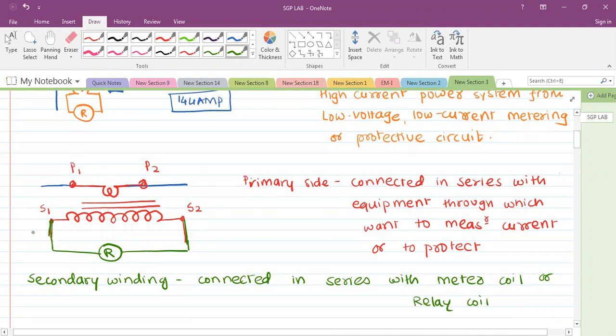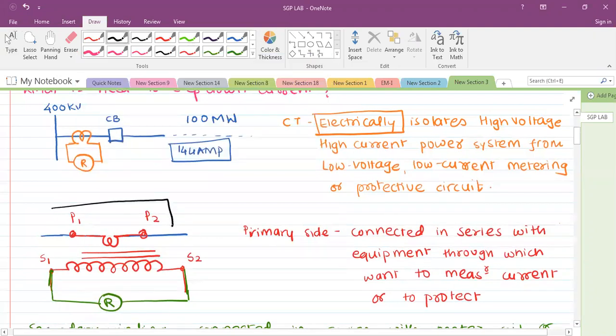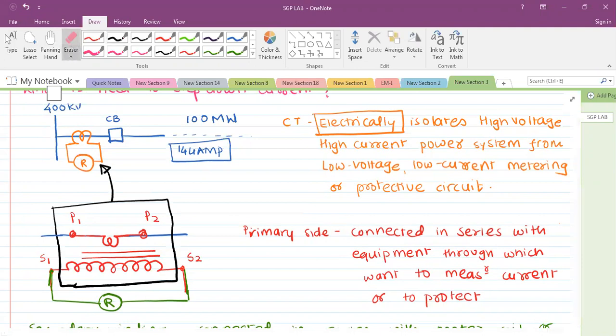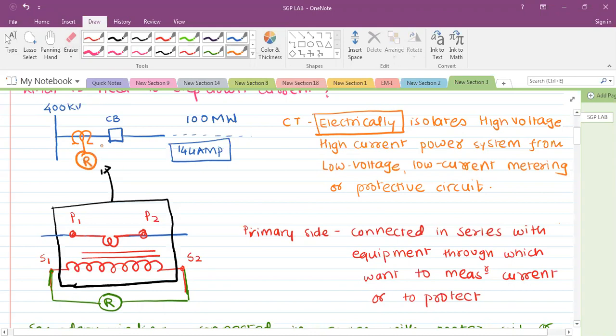Then understand, this is the symbolic representation that we will show every time for showing the CT. How is this connection symbolically represented in a single line diagram? It is represented in this manner. So understand, every time I draw the diagram like this, or probably in some book you will find it like this, or simply it may be like this also. It is the same thing, okay? So this represents the connection. Do you understand now how the CTs are connected? The primary winding is in series with the equipment, whatever equipment it may be, it may be a winding of a generator, transformer, or motor, anything, or maybe a line, and then the secondary is in series with either the meter or relay.